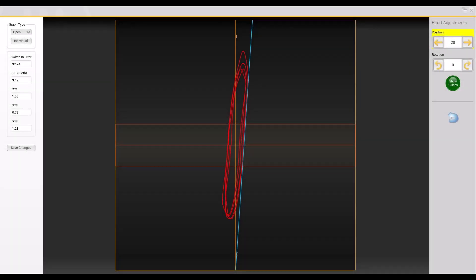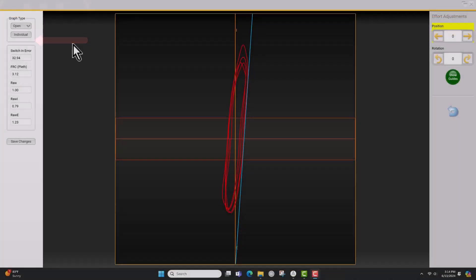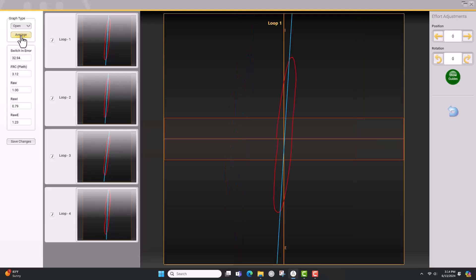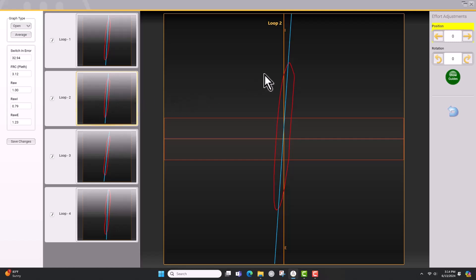An option for the airway resistance tracings is to separate each loop. Generally, each tracing has three to four loops superimposed on each other. If you wish to look at each individual loop, click on the Individual button in the upper left of the screen. This will separate each loop. You can now adjust each loop if needed. On the left side of the screen, click on the graph you want to adjust, then use the rotation arrows to adjust the line of best fit.